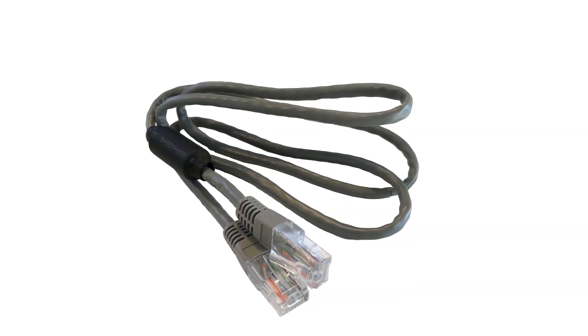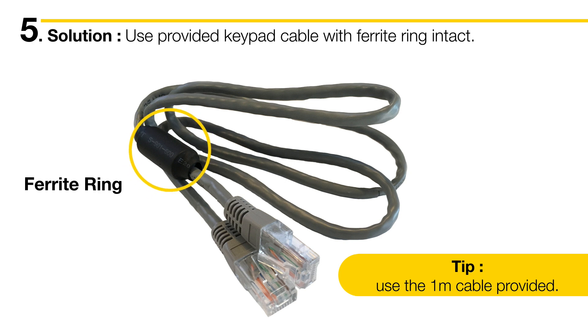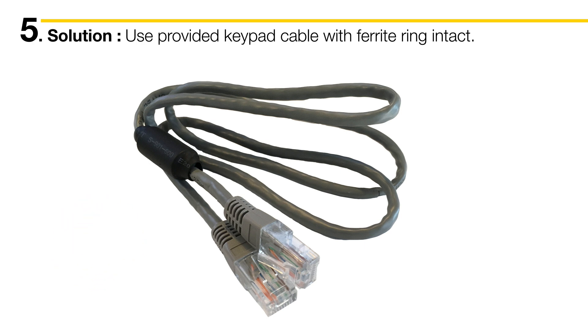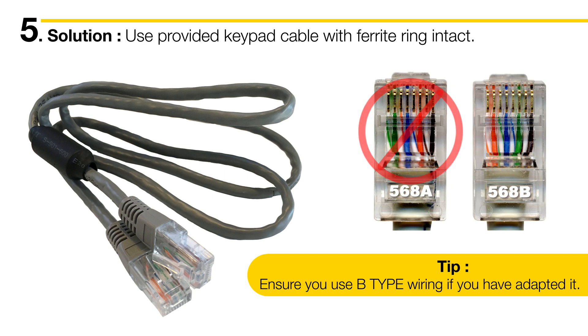The last common cabling issue is the keypad cable. Make sure you've used the one metre keypad cable provided and kept the end with the ferrite ring intact. The easiest way to access the coloured wires in the keypad cable is to cut and strip the cable. But if you've wired up your own female connector or tried to use your own keypad cable, you must use B-type wiring for the connectors, or your network communication will fail.